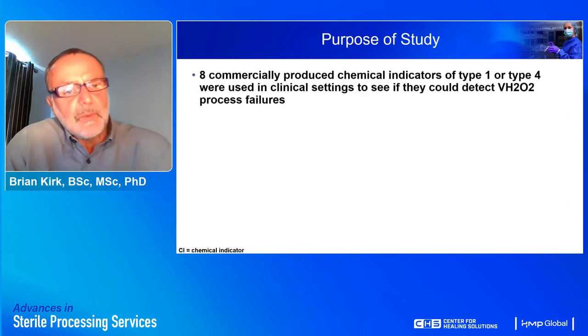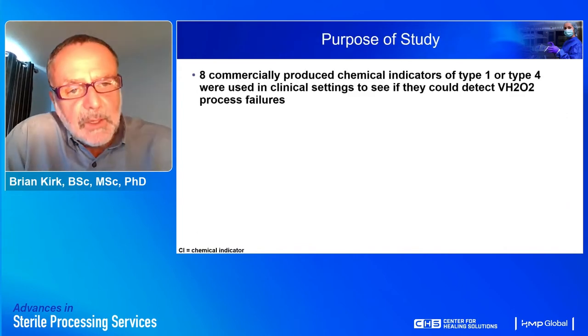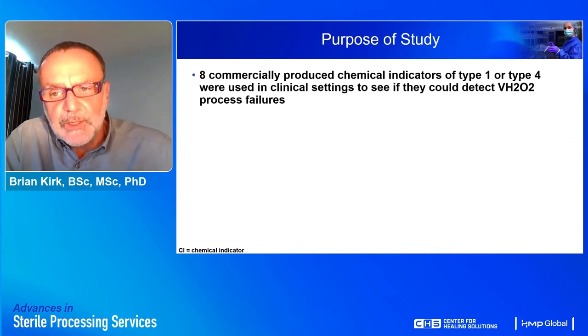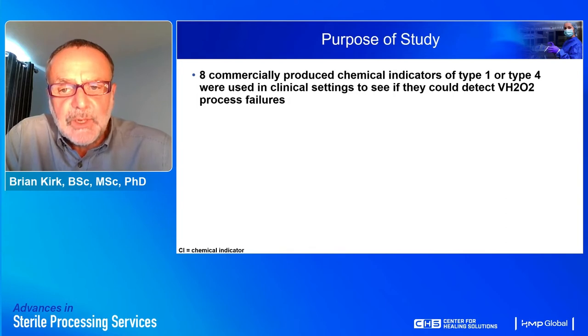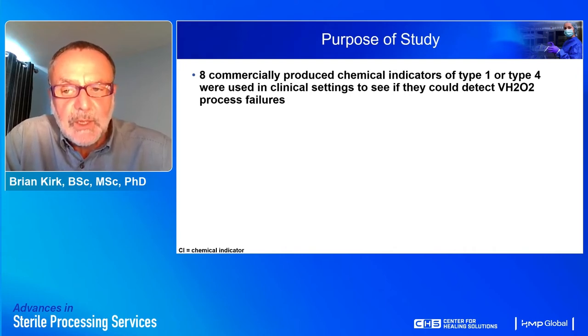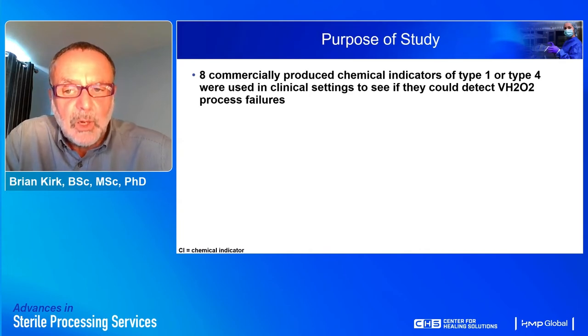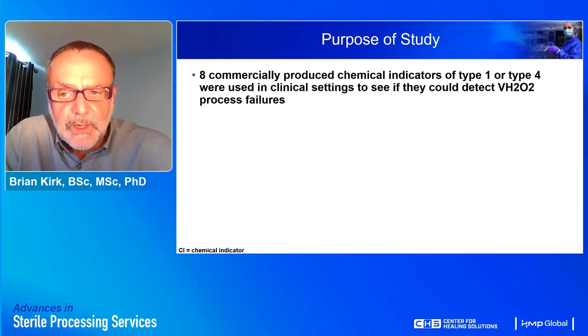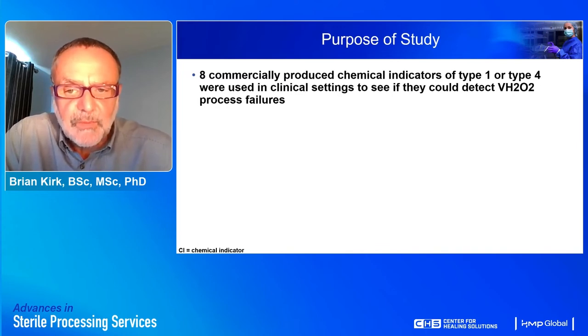The purpose of the study: eight commercially produced chemical indicators of type 1 or type 4 were used in clinical settings to see if they could detect hydrogen peroxide sterilizer processes operated according to the manufacturer's recommendations or operated outside of those recommendations — in other words, used off-label.